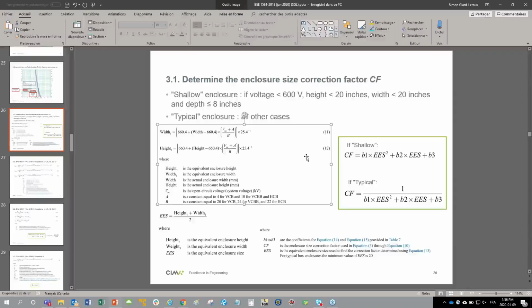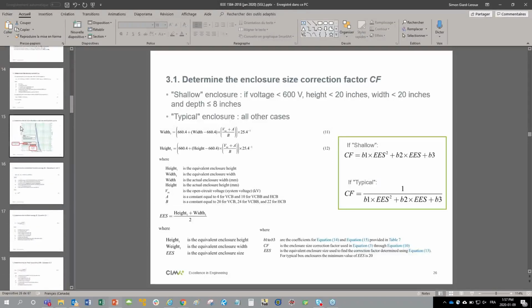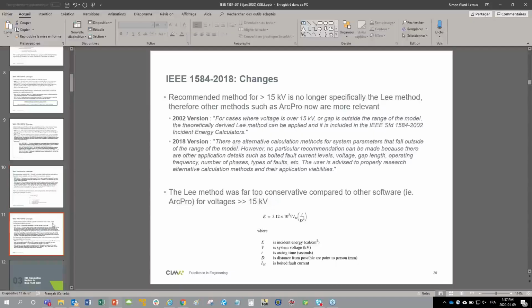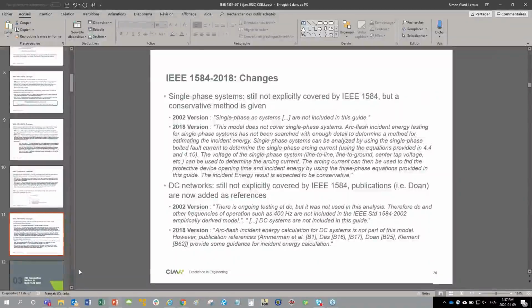Okay, so this is from David, and it's regarding single-phase systems, 2400 volts, 2500 kVA. It appears I can model this and perform arc flash calculations using three-phase formulas. From what you say, I'm not sure I'm comfortable with this. My guess is that you're typically looking at 120/240 panel boards with much lower transformers. Any thought about dealing with large single-phase systems? Well, with large single-phase systems, you can model them as three-phase systems and use the same equations. For example, in EasyPower, you can use your line-to-line voltage, and you will get conservative results, of course. Fair enough.